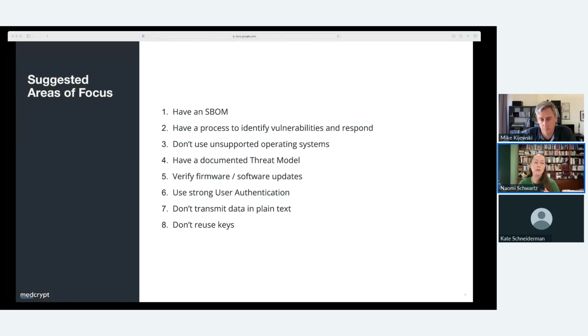So somebody asked earlier about auditing. Typically if FDA comes in and does an inspection, they're doing a standard quality system type inspection. They may ask to see those processes, and if you don't have them, they may ask you why you don't have them. Are they going in specifically to audit your cybersecurity practices? They may be. I know at least one instance where they did, and they issued a warning letter because of it. So there's no fuzzy area about whether or not you need to have these processes internally. And now you clearly need to document them and share them with FDA. It should be part of your quality system.